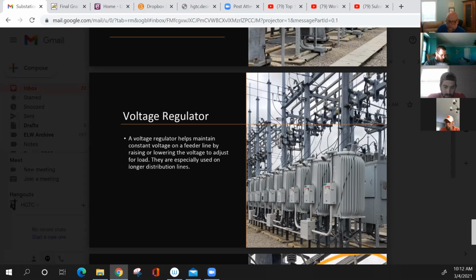Our new substations that we were building were this construction where the regulators were behind the breaker going out onto the field into the feeder. Duke, like I said, their substations were different. The older ones, my substation had 1 regulator, and it was behind the bus work between the low side switch and the bus was my voltage regulator. And it was what we call a regulated bus. It regulated the bus work for all the breakers in that sub.